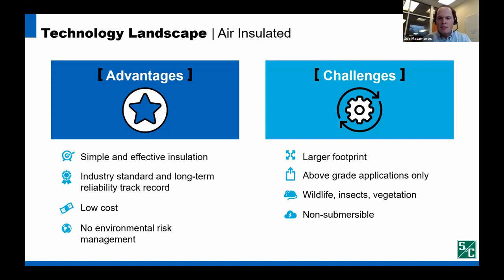Given the climate change policy and flooding concerns I mentioned earlier, you are likely seeing more applications where submersible gear is required. That said, floods will not necessarily damage air insulated gear. However, air insulated gear will not necessarily ride through floods and may require inspection and cleaning after flooding. Lastly, for protection applications, air insulated gear uses fuses. Fuses require crews to have sufficient training and use proper operating practices to replace fuses safely.